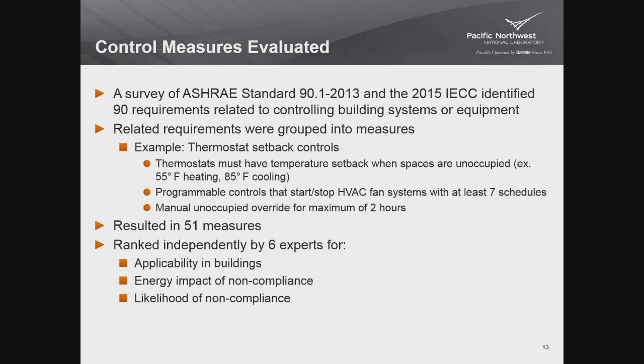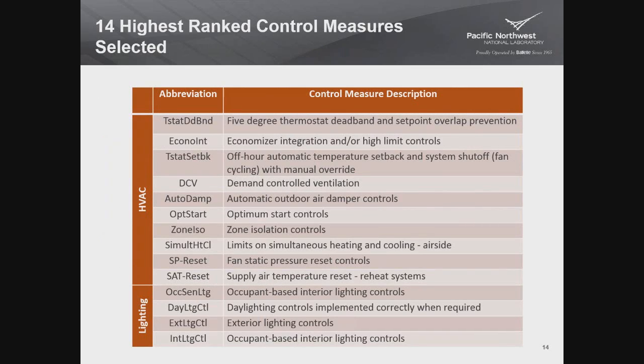Once we grouped those 90 requirements into measures, we had 51 measures. And we ranked those measures. We got together a group of 6 experts, and we asked them to rank those 51 measures in 3 different ways. Applicability in buildings, how likely are you going to find it in a building? The energy impact of noncompliance. If they don't comply, is it a big deal from an energy standpoint or not? And then the likelihood of noncompliance. Is it something that's so easy to get that you're almost never going to see it not complying? So they ranked each of those in each of those 3 ways, and from that, we took the top 15. And that's what this list is here.